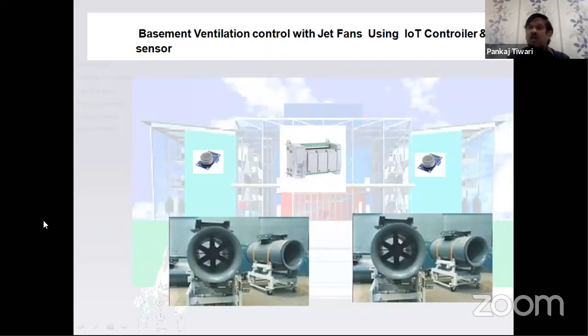For basement ventilation nowadays, it's a system basically using a programmable logic controller, PLC, or a DDC controller, connected to a series of jet fans as per the latest NBC. Based on the carbon monoxide level at that particular basement in comparison to the outside carbon monoxide level, they switch on the number of jet fans so as to maintain the carbon monoxide level in the basement.